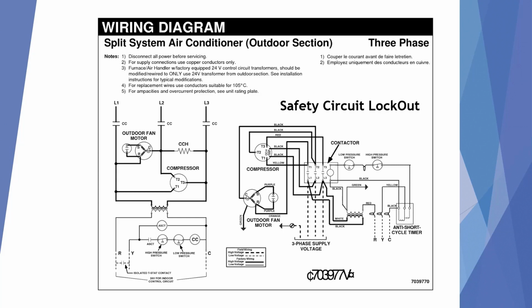You will notice in most wiring diagrams that the contactor is supplied voltage through a circuit that includes a low pressure switch, a high pressure switch, and possibly other safeties. These safeties need to be checked to make sure that power is flowing through these switches, energizing the contactor. If you've had a high pressure situation or a low pressure situation, that may be the problem why you can push the contactor in and everything runs fine. But when you try to energize it from the thermostat, the power is not going through that high pressure switch or low pressure switch because it's still open.